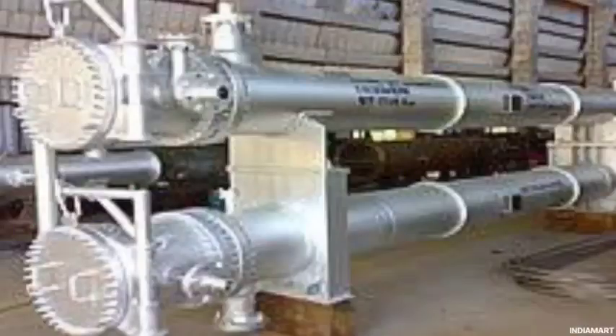First we design the top heat exchanger and get its center of gravity. Then we design the bottom heat exchanger and add the center of gravity of the top to the bottom exchanger. So the bottom heat exchanger knows there is something above it and accounts for its center of gravity and total weight. First you do the top one, then whatever CG comes, you apply that on the bottom.